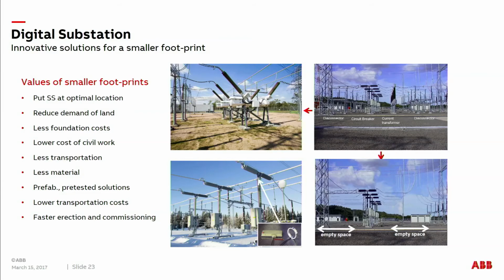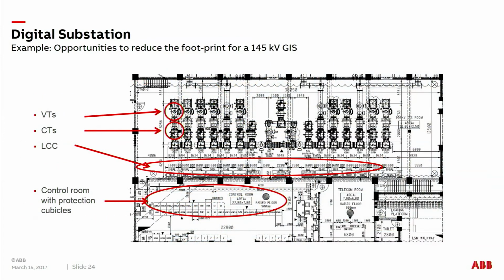Air insulated, you integrate current and voltage measurement into the primary equipment, so you really shrink the size. This is an example in a GIS substation. You have here a conventional voltage measurement transformer. This is a conventional current measurement transformer, and here you have all the control and protection cubicles. That will all disappear. So you will see that the current measurement is integrated into the combined sensor for current and voltage.